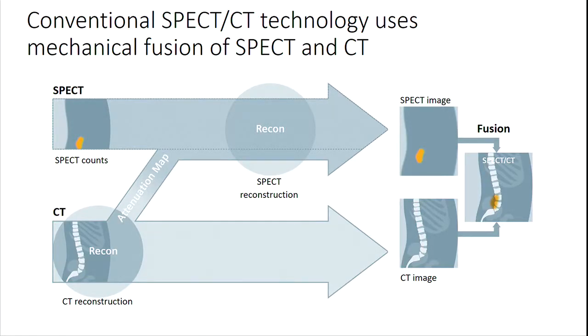To correct this issue there are plenty of new generation applications. Especially Siemens has come up with a very interesting application called xSPECT. Conventionally, the CT and the SPECT are corrected on a single platform, but the CT reconstruction is done completely separately, with its own set of corrections and its own calculation of the attenuation coefficient.